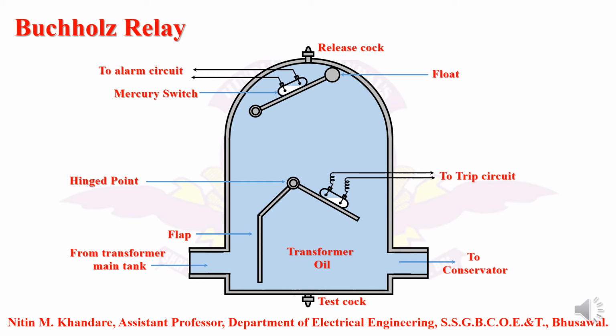in between that we are having a trap called the Buchholz relay. So what happens here, the gas will enter inside this system, but due to this flap it will be diverted upward towards the upward section. As this gas flows towards the upward dome, it deposits here, and as the gas gathers there, the float will be lowered down like this. So the float lowers down here, and when the float lowers down, both of the contacts of the mercury switch get closed, and the alarm rings there, and due to the ringing of the alarm the operator comes to know that some type of incipient fault is occurring inside the transformer tank. So immediate action can be taken for protecting the transformer from further damage.